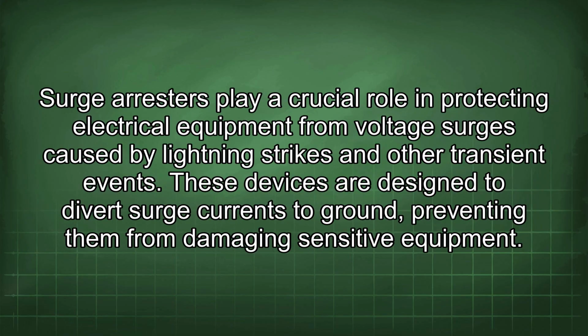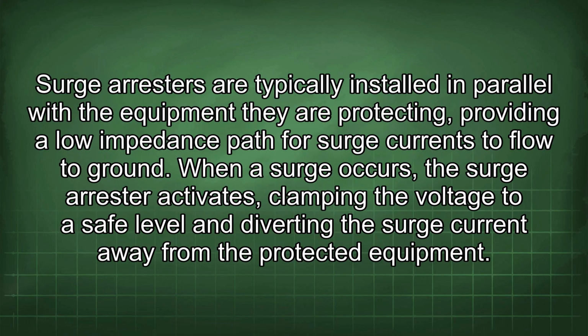Surge arresters play a crucial role in protecting electrical equipment from voltage surges caused by lightning strikes and other transient events. These devices are designed to divert surge currents to ground, preventing them from damaging sensitive equipment. Surge arresters are typically installed in parallel with the equipment they are protecting, providing a low impedance path for surge currents to flow to ground. When a surge occurs, the surge arrestor activates, clamping the voltage to a safe level and diverting the surge current away from the protected equipment.